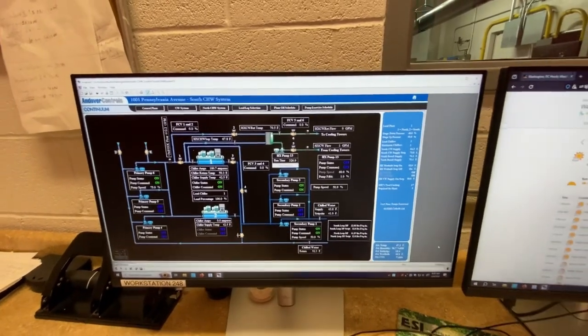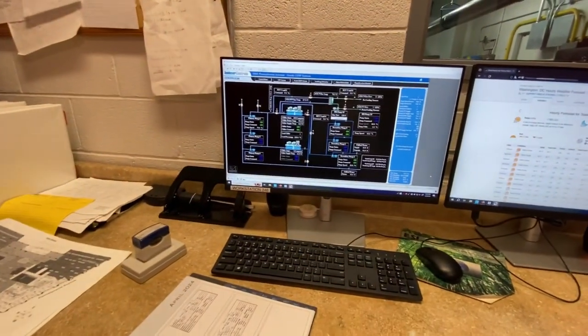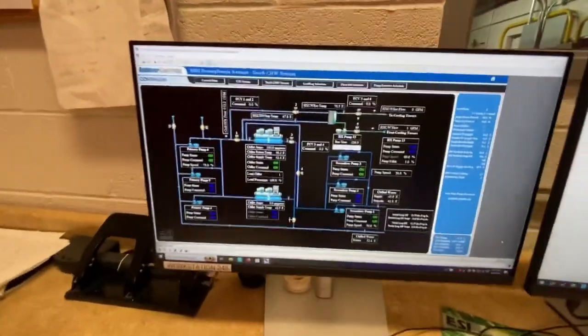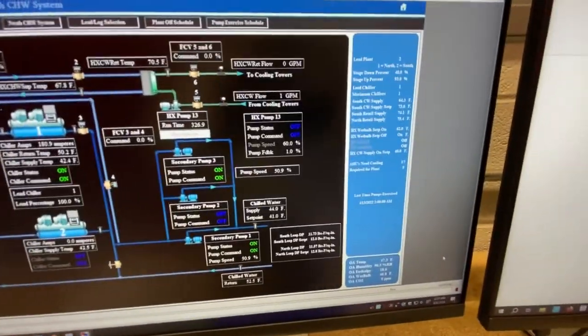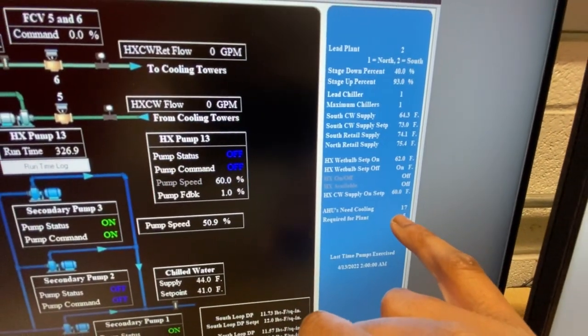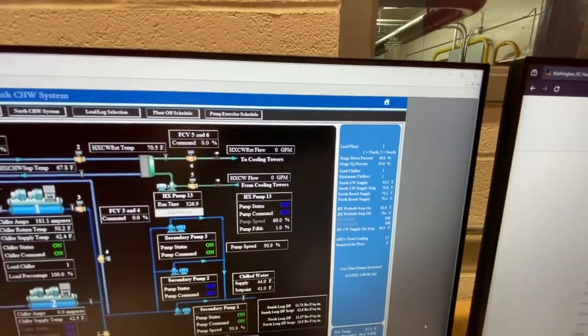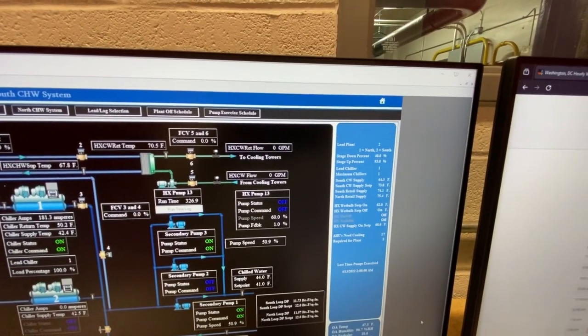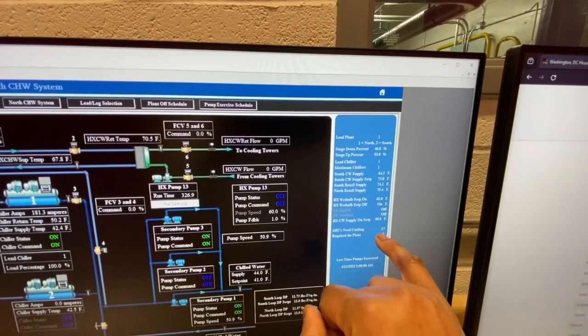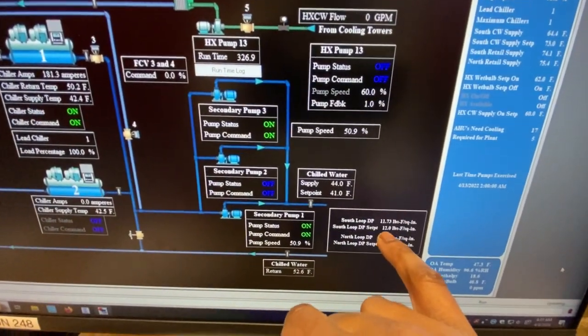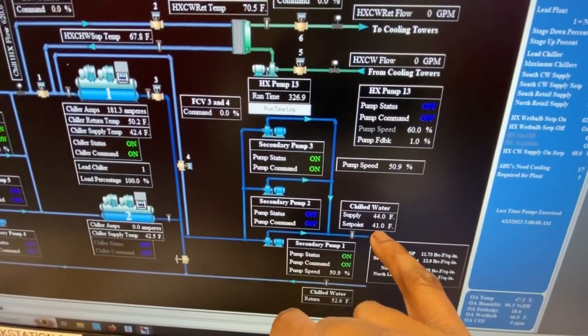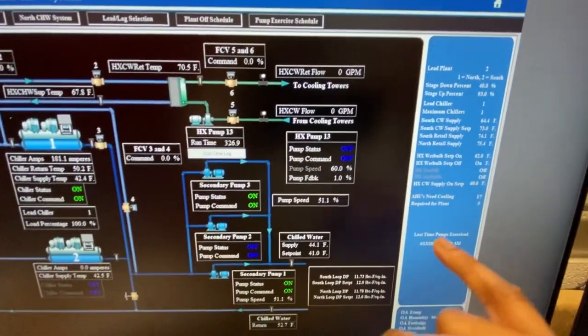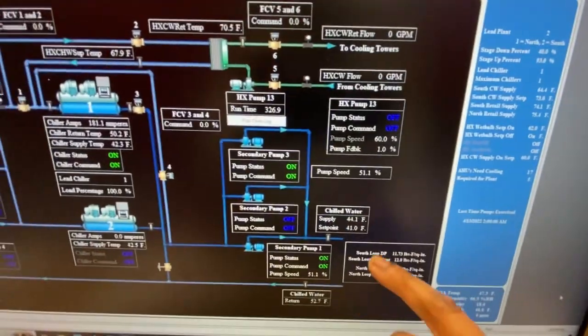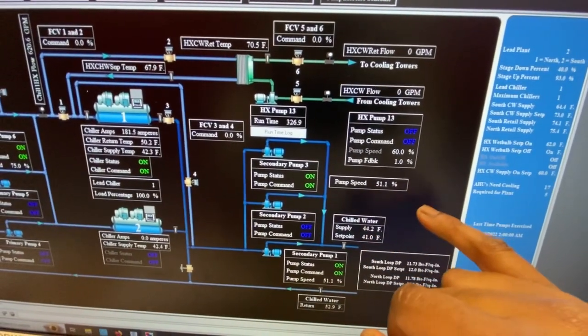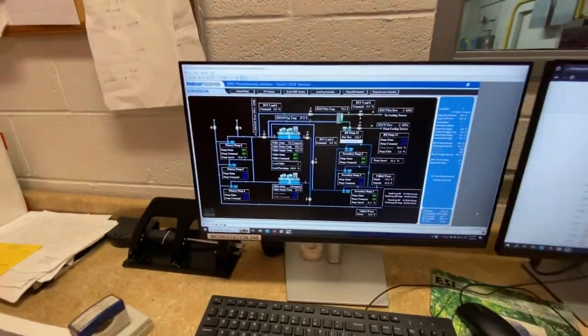I haven't looked at the electrical bill lately, but I believe it's good for such a big building and old equipment, so I think we're doing well. Right now we have 17 air handler units running. We have close to 100 air handler units. On a day-to-day basis, sometimes we get up to 55, 60. So right now we are very low, and that's probably the reason why I'm keeping up with the DP, even though it dropped by 1 right now, and the supply is that low. As more air handler units come in, I will start seeing the supply temp go up a little bit more, because now you have more boxes that are open trying to cool the office.